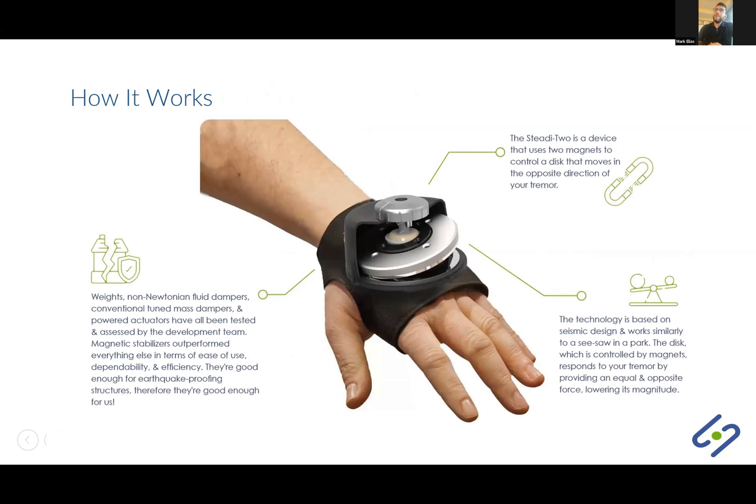Now, I'm going to delve into how the technology works. This technology was actually inspired by earthquake design. High-rise structures today use something called the tuned mass damper to control the vibrations that earthquakes create — they consist of a spring and a mass that move against earthquake vibrations. The Steadi-Two technology took tuned mass dampers and adapted them to hand tremors. The device uses two magnets to control a disc placed on top of the hand. Similarly to a seesaw, the disc responds to your tremor by moving in the opposing direction, creating an equal and opposing force to reduce the tremor amplitude.